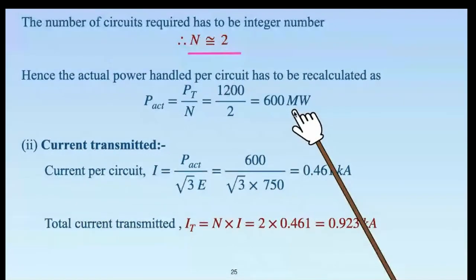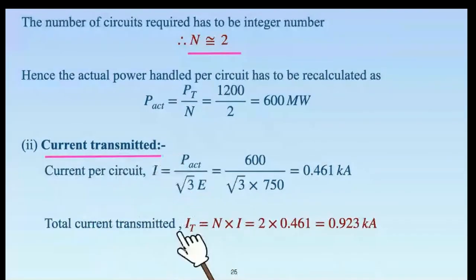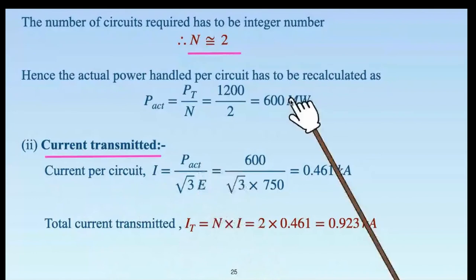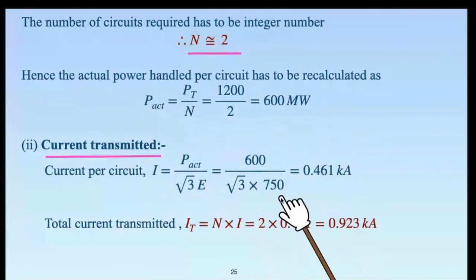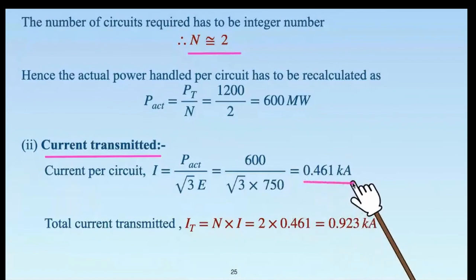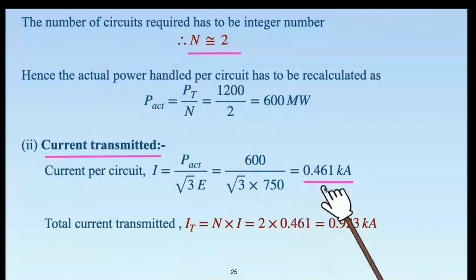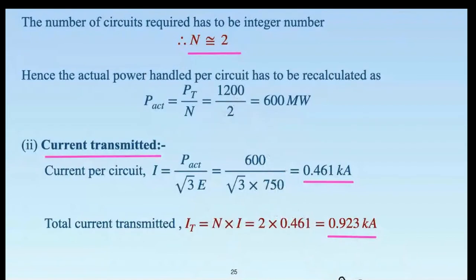The current per circuit at 750 kV is calculated as I = P / (√3 × E) = 600 / (√3 × 750) = 0.461 kilo-amperes. The total current transmitted across both circuits is 2 × 0.461 = 0.923 kilo-amperes.